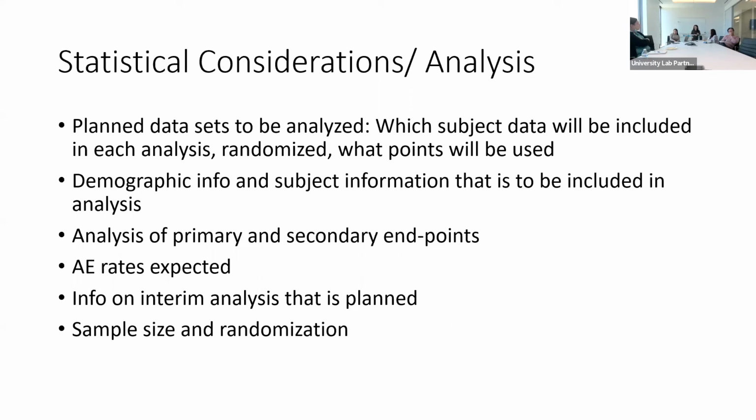So when you're evaluating pulse oximeters, they require that the data is not all skewed to males or all skewed to females. They require a breakdown of skin tones, right? Because light absorbs differently on different skin tones, right? They want to know that you have a range of ages, right? These are all details that they want when you're doing your data analysis.